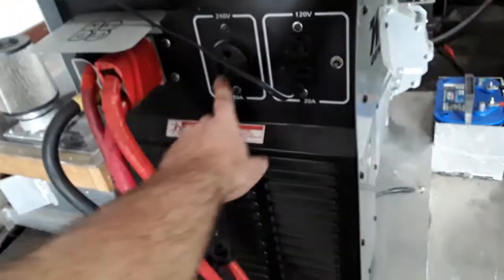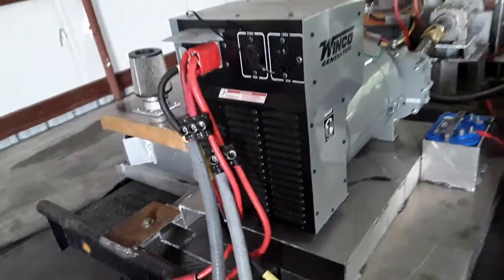This right here is just the neutral and the ground, and these are both hots coming out right here. This is 50 amp output, 120 volt output, and this is one hot leg, and this is the other hot leg. This is 240 volt single phase at 50 kilowatts, which is 208 amps.